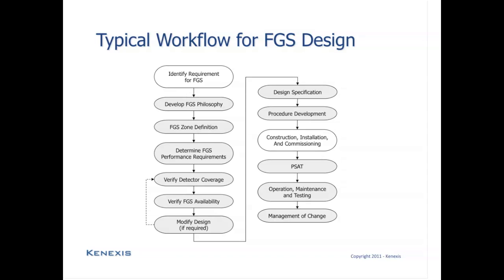After the design has been specified, procedures need to be developed for maintaining and operating the system. So operations procedures for how to interact with the fire and gas system in normal situations and also emergency situations, and also procedures for maintenance of the system, including testing procedures and other preventive maintenance tasks. After the design has been completed, the construction, installation, and commissioning phase occurs, where the equipment is installed in accordance with the FGS safety requirement specifications.